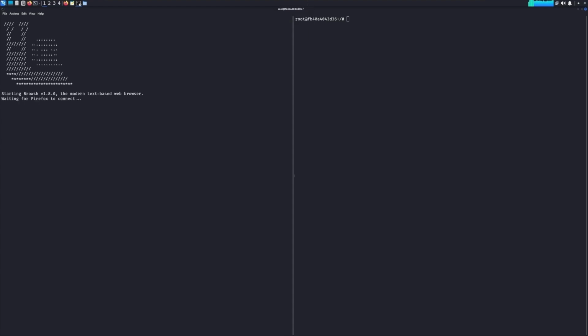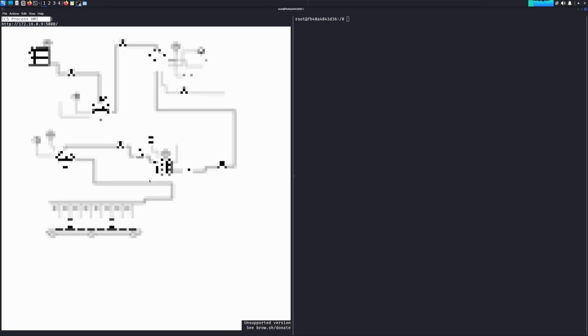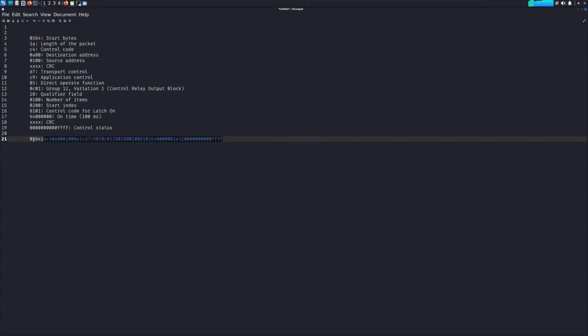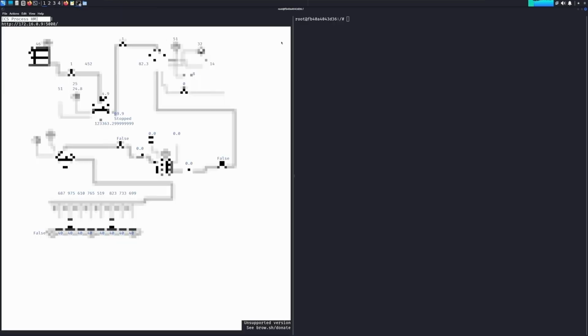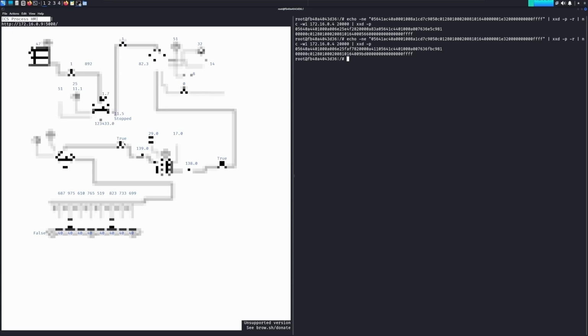Check the HMI to verify if the value is modified or not. Run the write payload again and check the valve status. It was set to true and again reset to false. This is because our payload sent it to set for 100 milliseconds. Let's run this payload in a loop to make this valve open all the time.